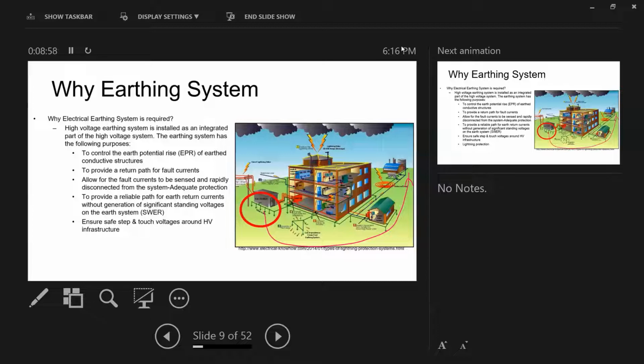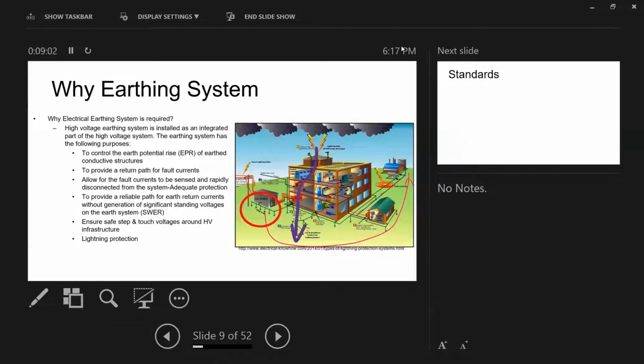One of the most important topics that we're going to spend some time on is step and touch voltage, and at the end, lightning. You want to make sure that when lightning strikes, guys, when you talk about lightning, you're talking about maybe 100 kiloamps. 100 kiloampere, it's a massive power. It's not small. It's hitting your building, your high voltage infrastructure, your communication, telecommunication line. You need to be able to actually design a proper earthing system to absorb this massive energy.